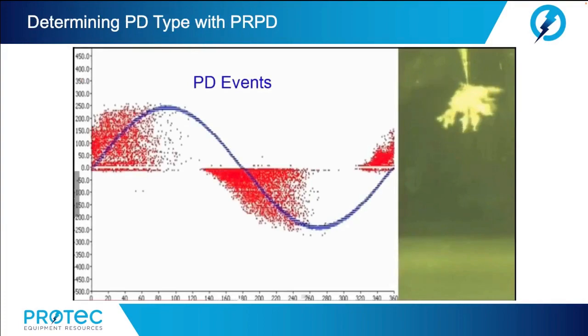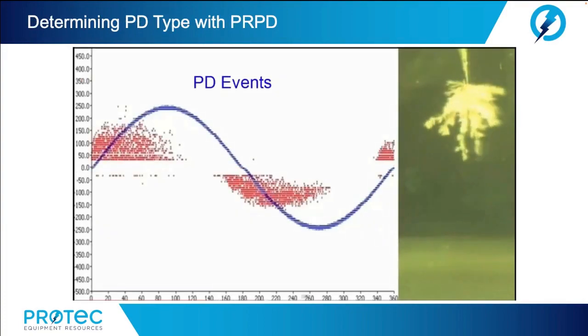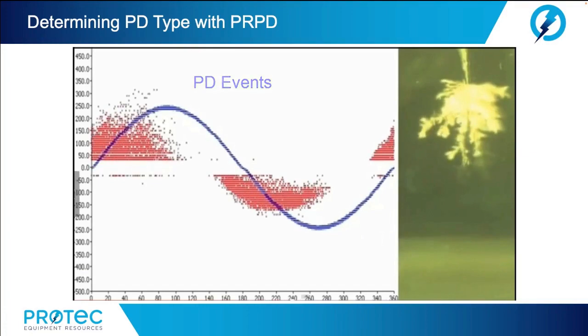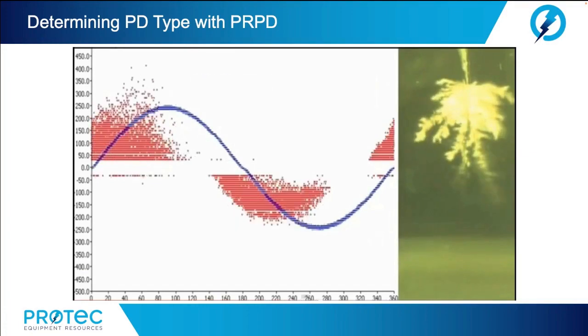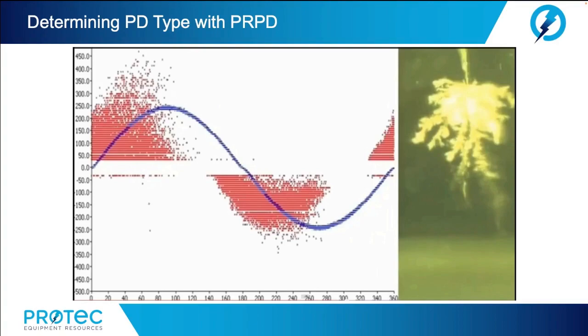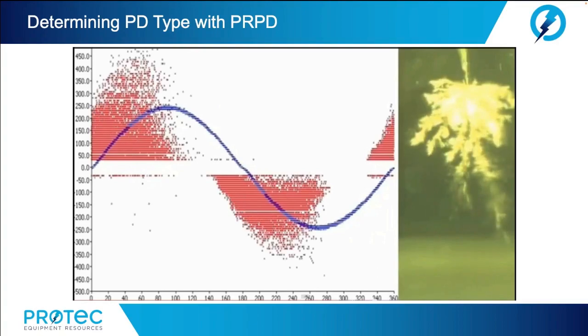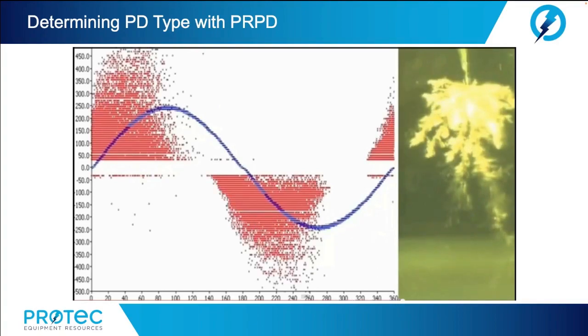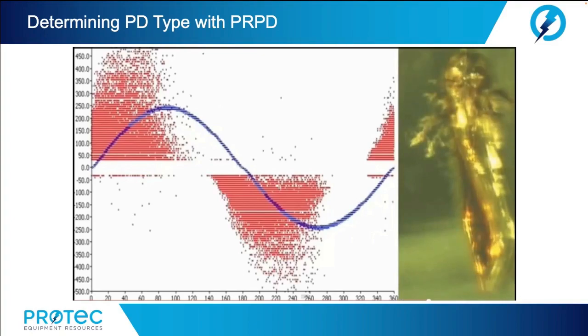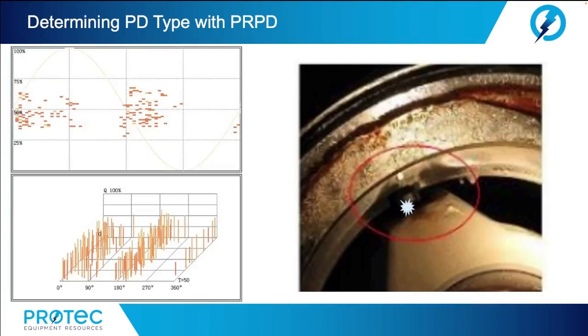Now, in addition to discovery and identification of PD activity, the PRPD method can be used to determine the type of partial discharge activity that is occurring. Each type of partial discharge has a certain pattern in the distribution of pulses. The charts that we will review show the typical patterns for each type of partial discharge. So, here's an example of floating electrode partial discharge.